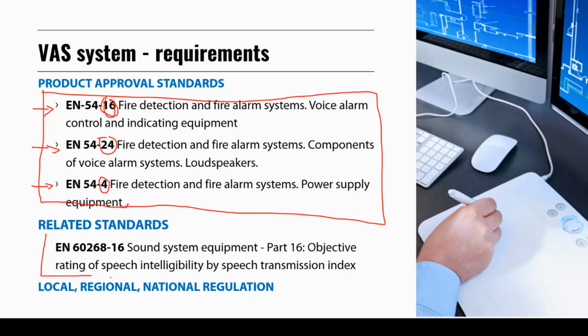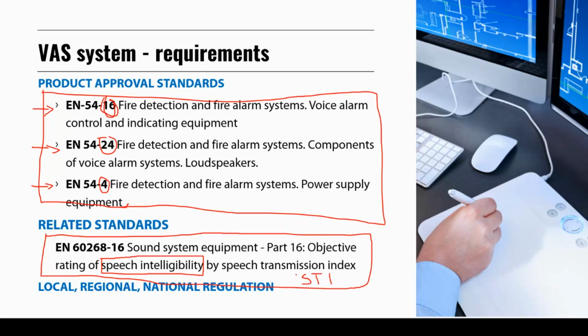Now we will also speak a little bit about one detail that is super important when it comes to the approval of the final commissioning of the system, when it's already installed in the building. And that is the standard that defines a parameter called speech intelligibility. Speech intelligibility is defined by the speech transmission index, or in other words, STI. And the STI is one of the most important output parameters of the voice alarm system after it's commissioned and installed.